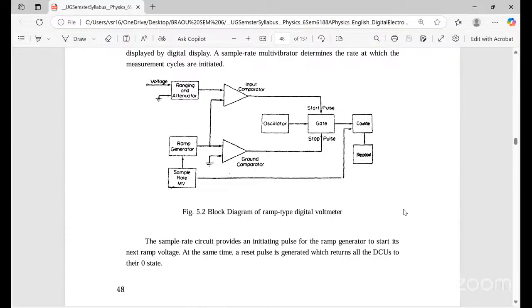The sample rate circuit provides initiating pulses for the ramp generator, and it starts its next ramp voltage. At the same time, the reset pulse is generated, which returns all the display counting units to their zero state.